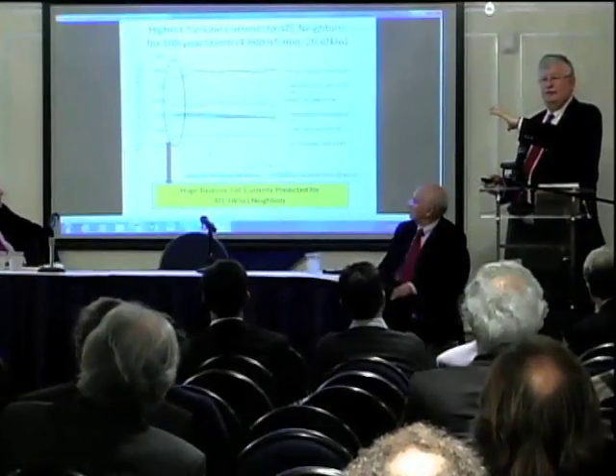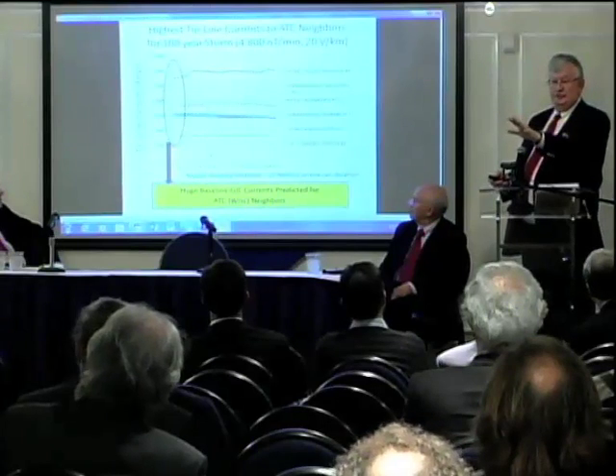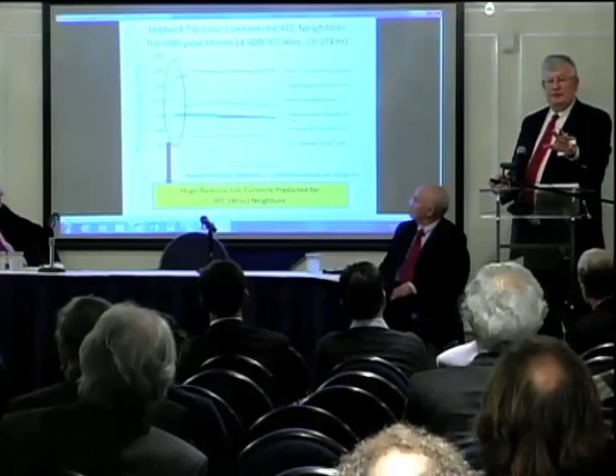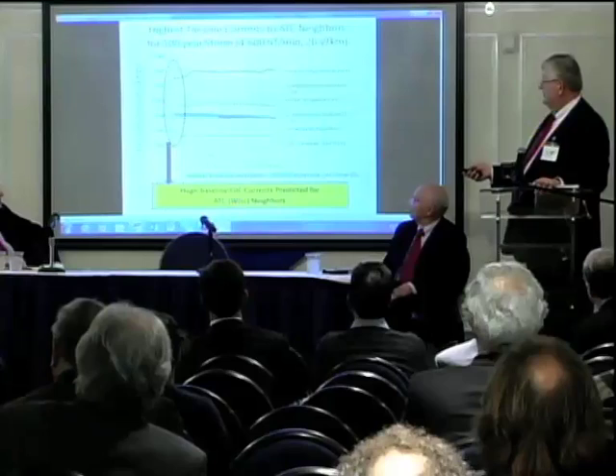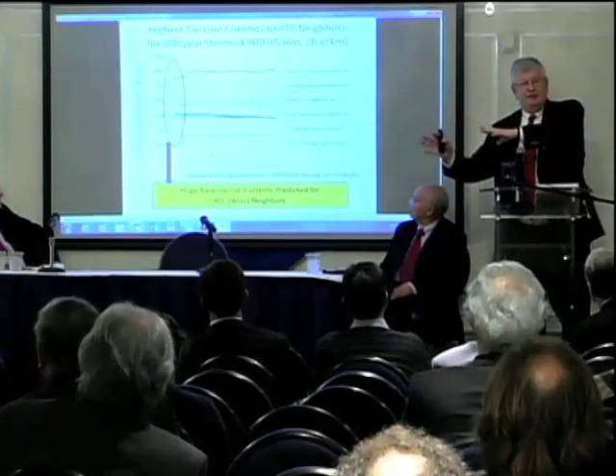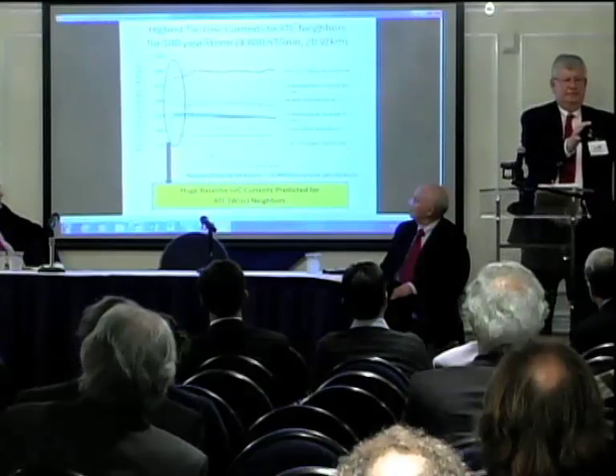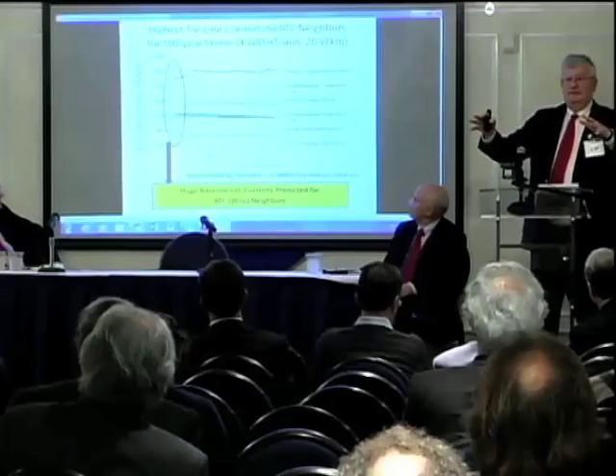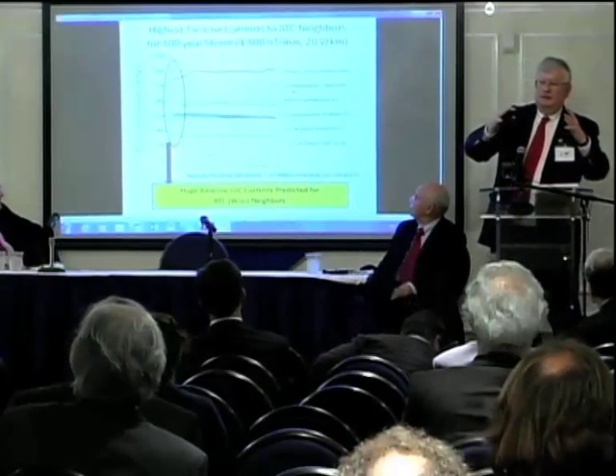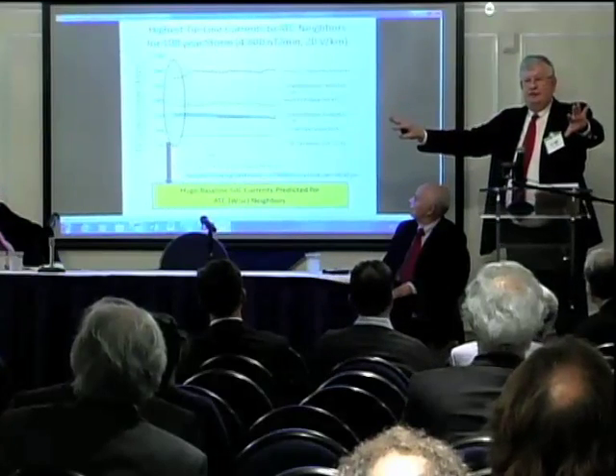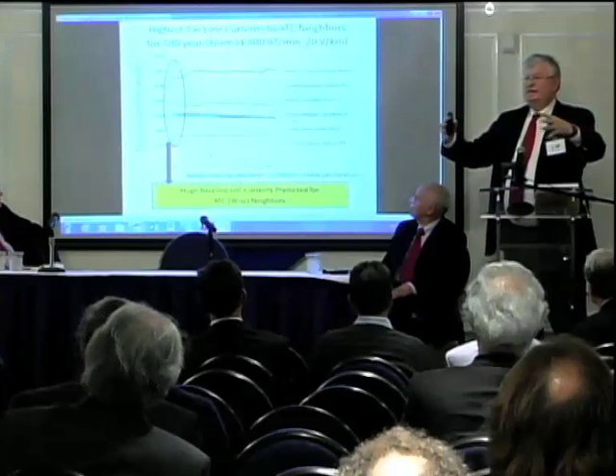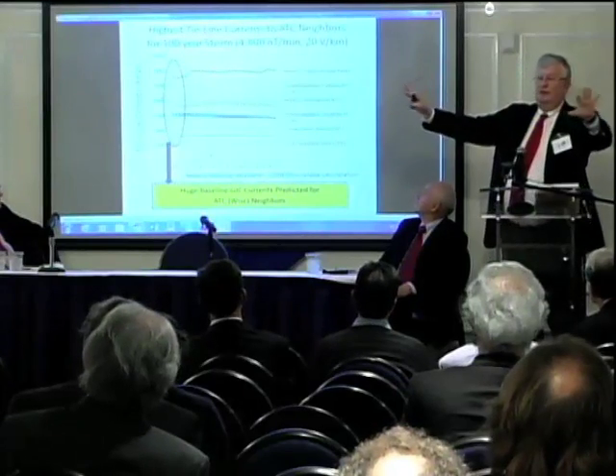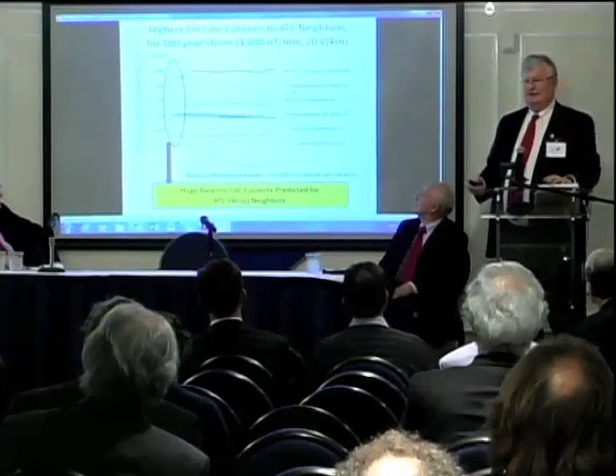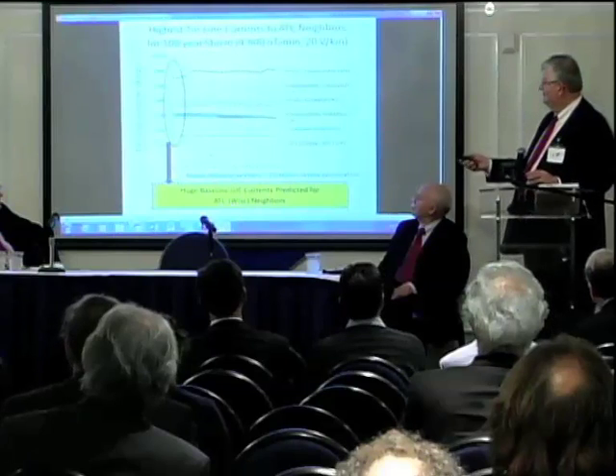Here's another really interesting graph. Remember before I said actual data could point to 2,000 amps of current in the neutral. So we simulated with Power World. Over in Wisconsin, we said, what's the effect on the neighboring utilities if we blocked Wisconsin? Because we've heard from many utilities, oh, well, if we block, it'll push it to the neighboring utilities. Or vice versa, it doesn't do us any good to block until all the neighboring utilities do. Well, let's take a look at that. We'll call this a myth buster.